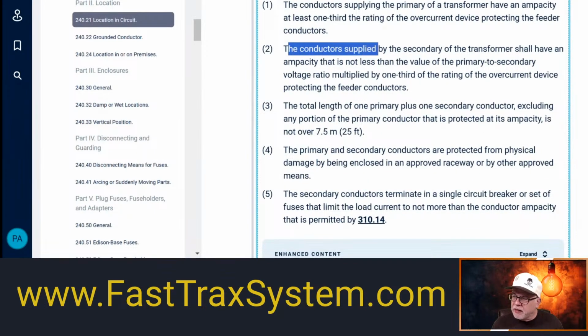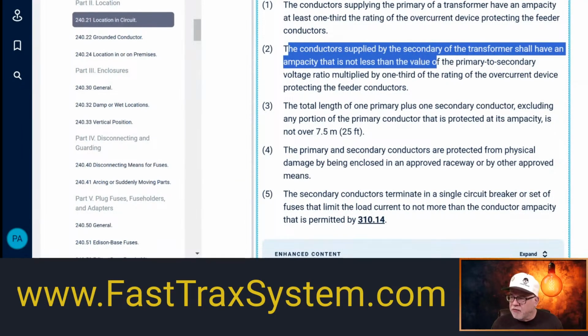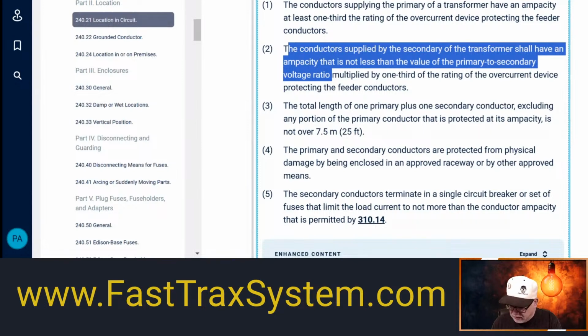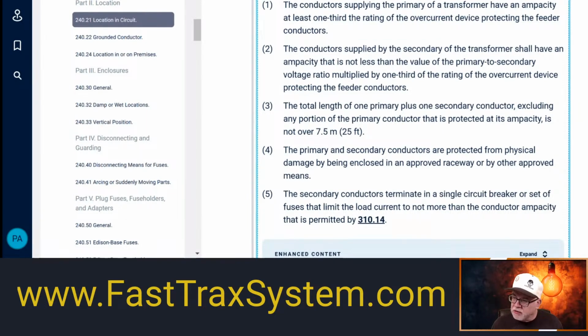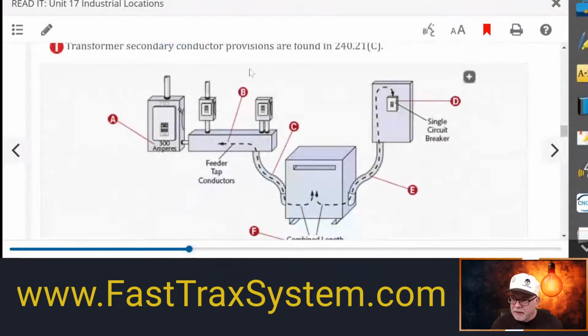Next, it says the conductors supplied by the secondary of the transformer, okay, shall have an ampacity that is not less than the value of the primary to secondary voltage ratio. So the primary is 480. The secondary is what? 208. Okay, so in order to get that ratio, we're going to go 480 to 208 is 2.307. So we'll just say 2.30. We'll just say 2.31. We'll round it up to get it to the smallest value. Okay, so 2.31 is our ratio. So it says the conductor supplying the secondary of the transformer shall have an ampacity. Okay, so that is dictating the minimum size for these conductors here, which may be larger depending on our transformer and loads, but that's a minimum factor. So can't be less. Okay, so we're sizing these.